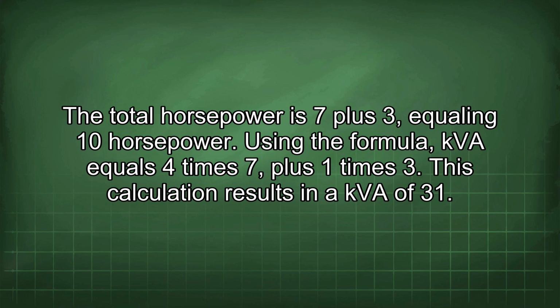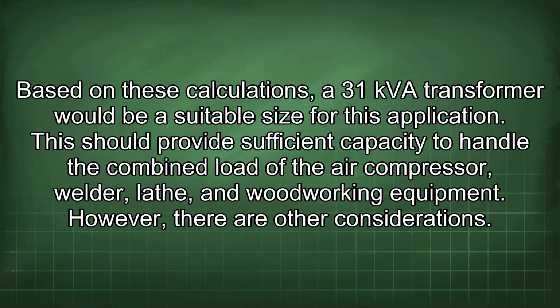Using the formula, kVA equals 4 times 7 plus 1 times 3. This calculation results in a kVA of 31. Based on these calculations, a 31 kVA transformer would be a suitable size for this application. This should provide sufficient capacity to handle the combined load of the air compressor, welder, lathe, and woodworking equipment. However, there are other considerations.